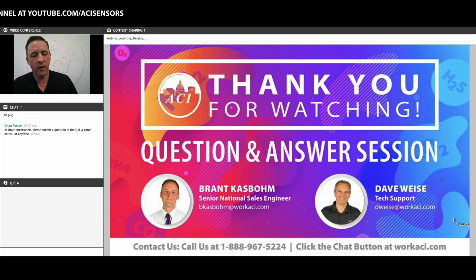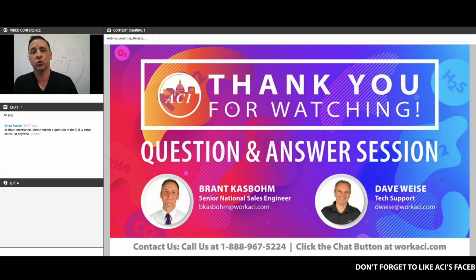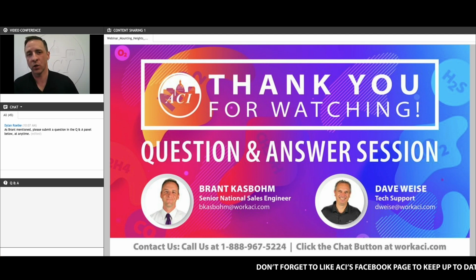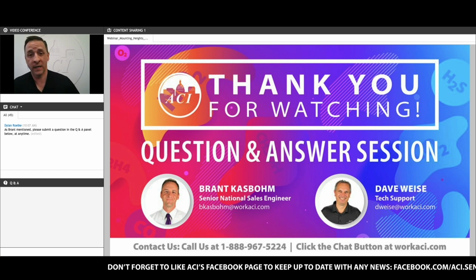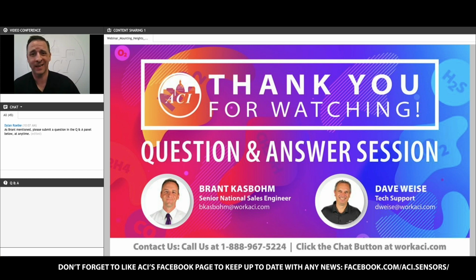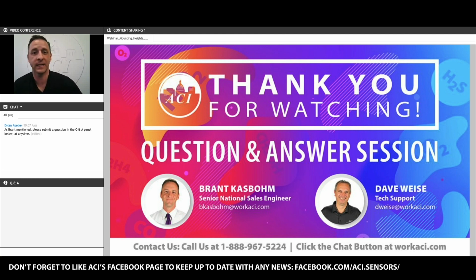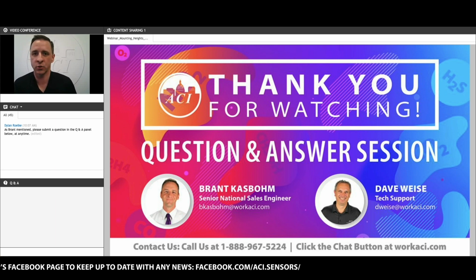So I encourage you to reach out to us for project pricing. We can be very competitive for you. Another question along those similar lines, why do some sensor manufacturers recommend mounting NO2 sensors in the breathing zone? That's generally a cost-saving mechanism for ease of install, because, like I mentioned at the start of the presentation, there's no national OSHA or ASHRAE code for sensor mounting heights. So sometimes people just recommend putting everything in the breathing zone because that's where people are breathing. And I understand why that recommendation would be there. However, again, we recommend mounting the sensors based on the actual chemical density or weight of that gas, because that's where that gas is going to pool and build up, and you're going to have the highest concentrations of these toxic or combustible gases.